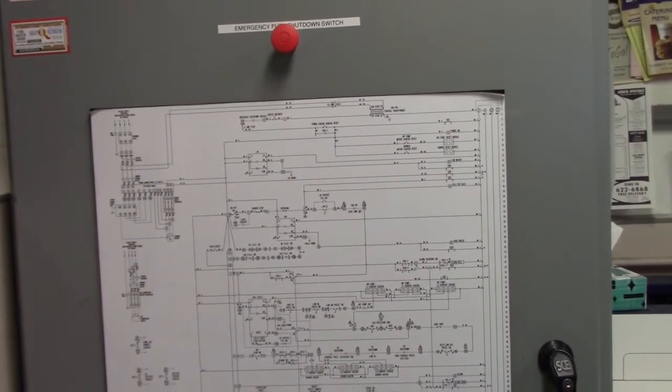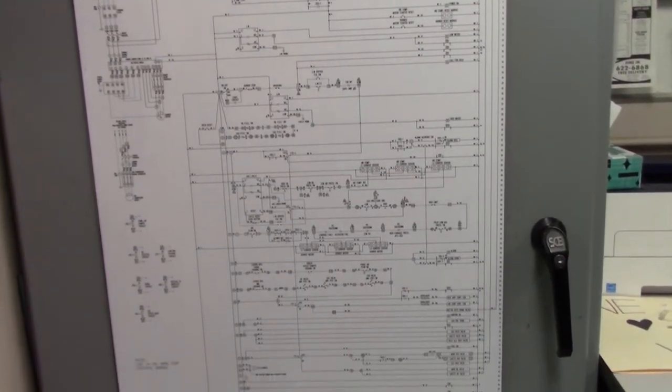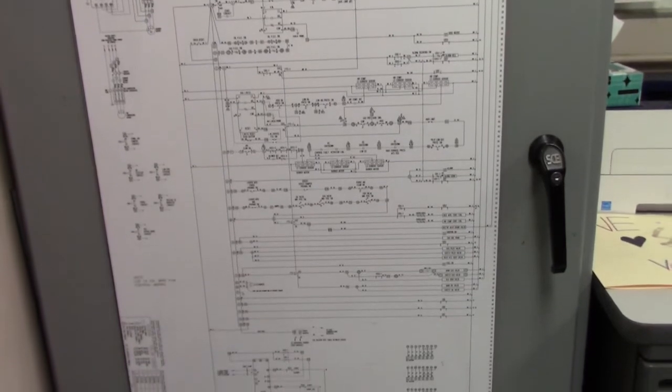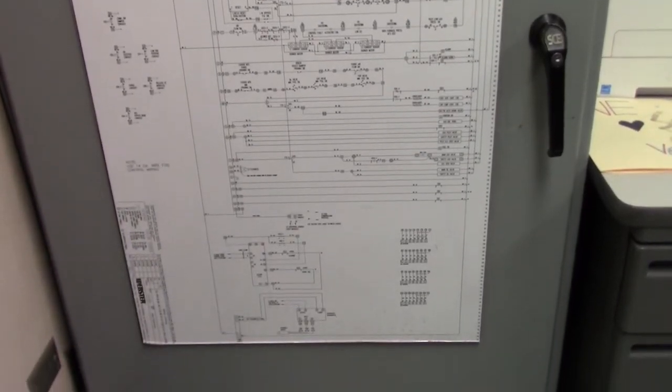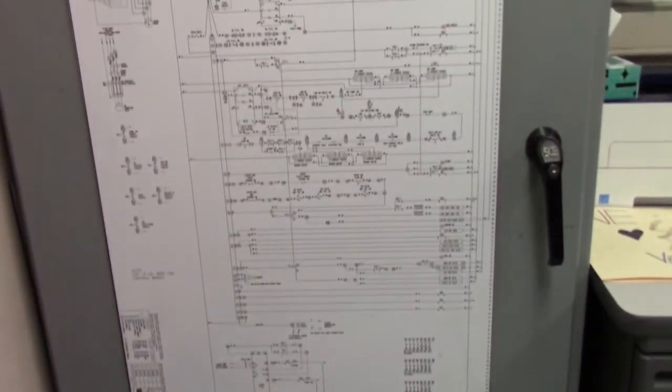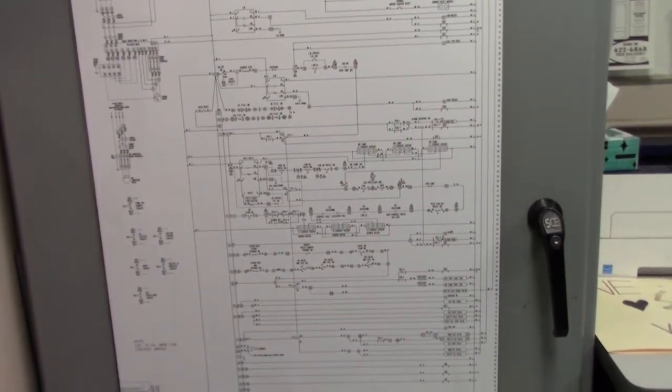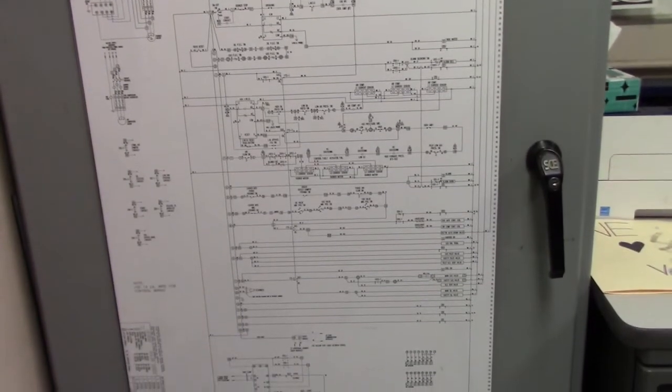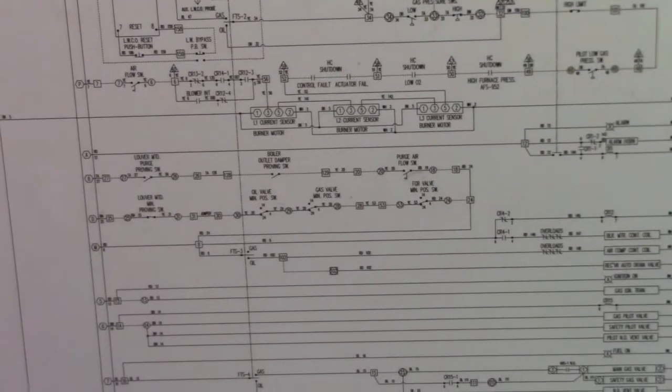So in the control room, we have a schematic of the boiler control system. If we use that indication on the FireEye, M8 limit open, we could use this schematic to narrow down the possible components that are causing the problem. So we need to trace out on this diagram the M8 loop.